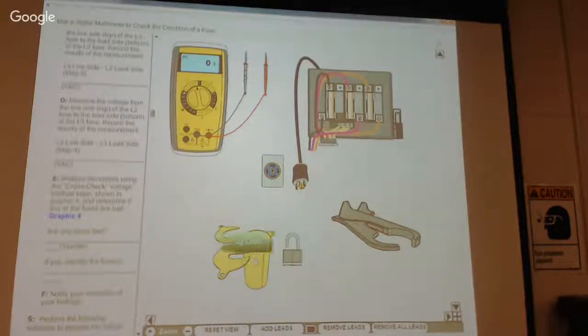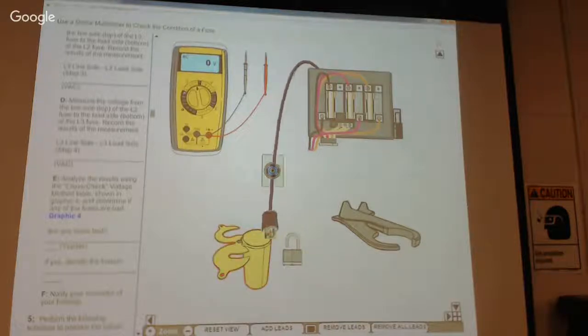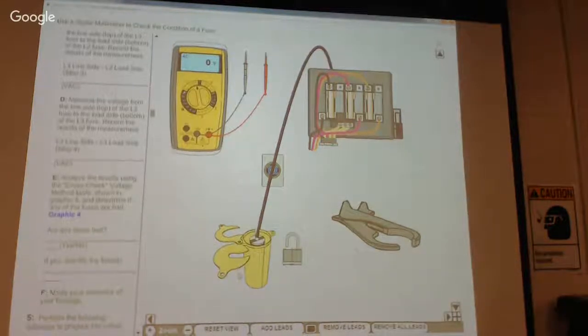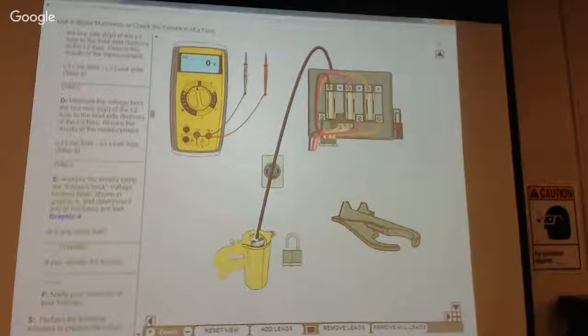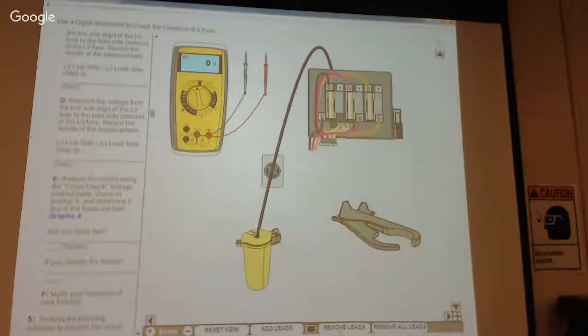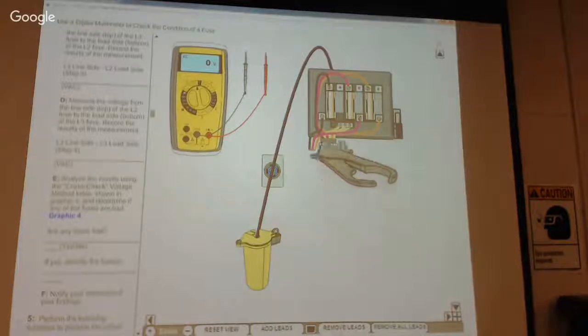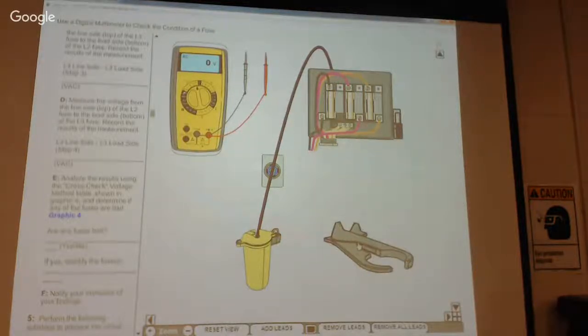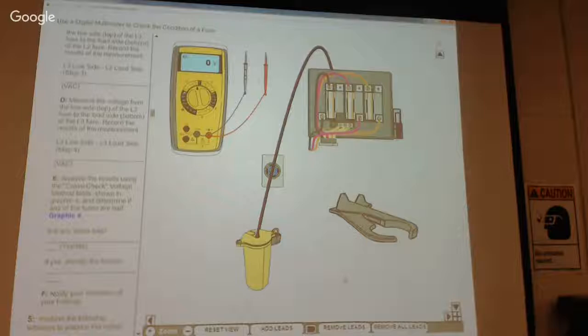We're going to drop that in there. That's how that works. We're going to seal it up. We're going to apply the lock. We're going to get our fuse pullers. Now, the reason we use fuse pullers is we don't want to damage these, okay? But in the real world, you'll see people pry them out, grab them with channel locks and everything else.